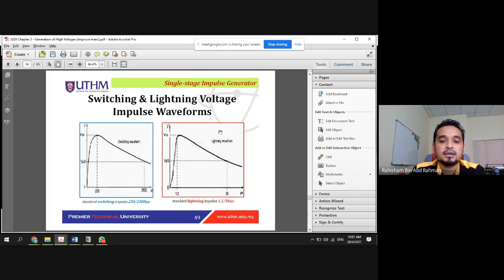As compared to the lightning waveform, there will be 1.2 and 50 microsecond. The lightning impulse is faster, the transient period is quicker, because switching is about 100 times that of the lightning impulse.